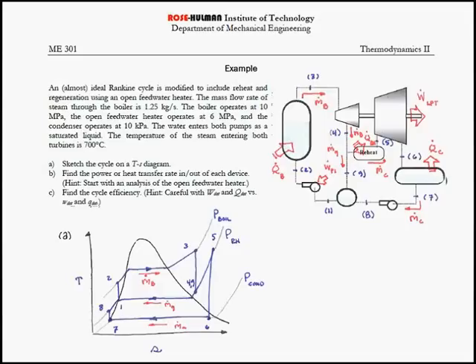And here's where we take some stuff, bleed it off, have it go through the intermediate pressure through the open feedwater heater, and the remainder is reheated back to the same temperature, lower pressure than that of the high-pressure turbine. That is expanded through the low-pressure turbine, 5 to 6 across the low-pressure turbine. Those two streams come together. They mix so that the stuff going into the boiler is a higher temperature than it was before, and the boiler doesn't have to add as much heat transfer.